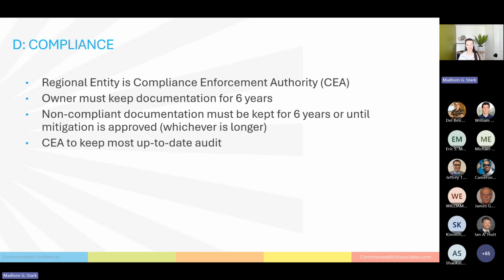Now, as far as compliance goes, these compliance enforcement efforts fall under the regional entity that the generator belongs to. The owner is responsible for keeping documentation on hand for 6 years, so that will go through multiple PRC coordination efforts. In the event that you're found non-compliant, you have to keep it for 6 years or until you fix it, whichever is longer. Hopefully it doesn't take you 6 years to get your generating unit compliant, but it's whichever of those 2 periods is longer. The Compliance Enforcement Authority, or the CEA, will only keep the most up-to-date audit, so you cannot rely on them to keep the documentation that you need to remain compliant. The owner is responsible for keeping that documentation on hand.